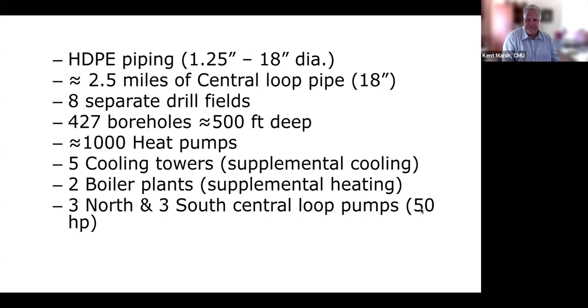So each of these things that I'm going to talk about, I'm going to try to describe in greater detail. But from the big picture, our TIN is comprised of miles of high-density polyethylene piping. The diameter of that piping is as small as 1.25 inches, and those are the pipes that we drill down into the earth and that we use to exchange heat between the ground and our central loop. And those pipes vary in size from 8-inch diameter up to 18-inch diameter.